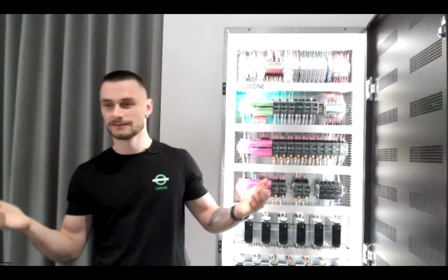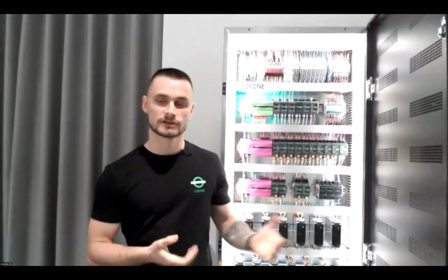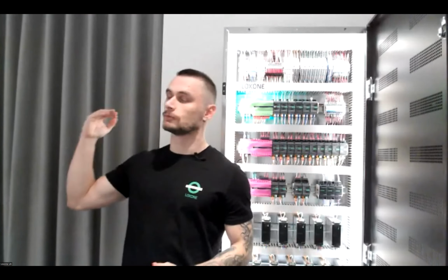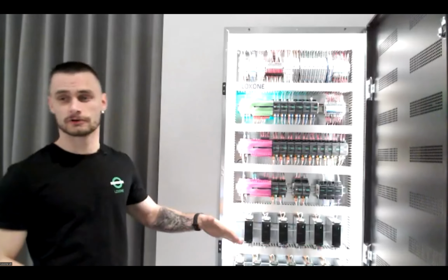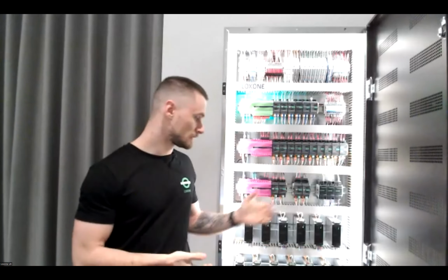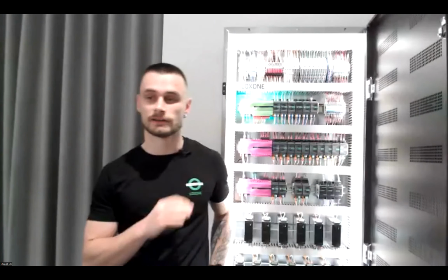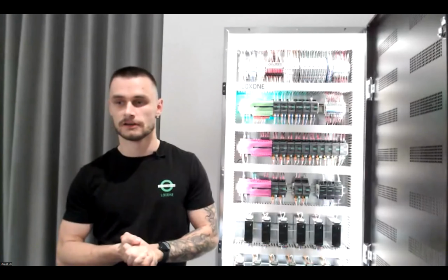So we had our grand opening. On our grand opening, we had a lot of lights on, different colors. We had music at a very loud level. And we really tested out the space to see what is possible, how much energy we're actually using, and what is the maximum that a whole panel is going to be drawing. Now, this panel with 135 amps of power supplies absolutely never went above 35 amps for the total consumption of the whole space.